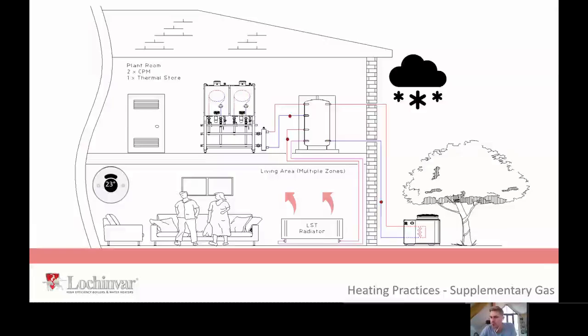A lot of people like this approach as well because it gives you a massive reduction in your initial capital. If you've got a site that's got gas anyway, just for reference, a 60 kilowatt wall hung boiler would cost about £3,000. A 60 kilowatt air source heat pump plant cost would be about £25,000. So from a capital point of view, if you've got the ability to have your second point of failure as a gas product rather than a second heat pump, capital wise, it's going to make sense. Unless you've not got gas infrastructure on site, in which case digging a gas trench is pretty expensive. But these are the considerations you make as designers on an application by application basis.